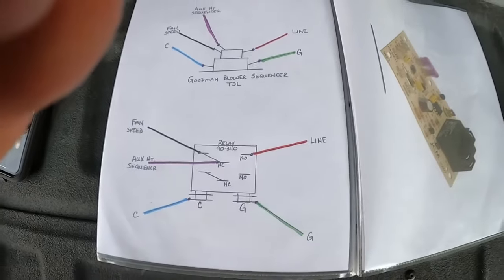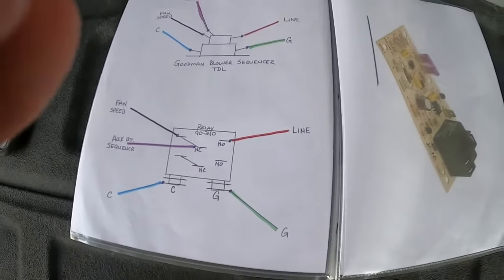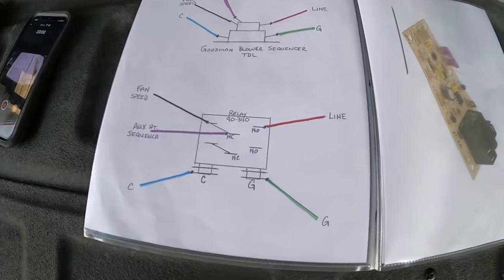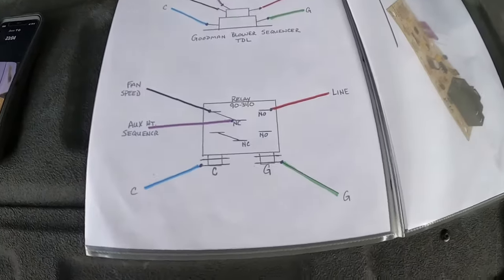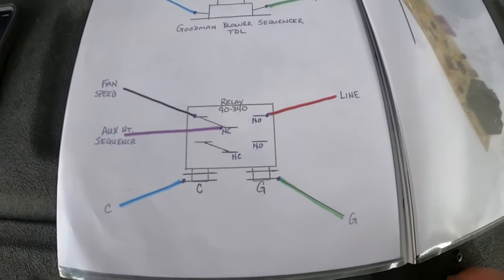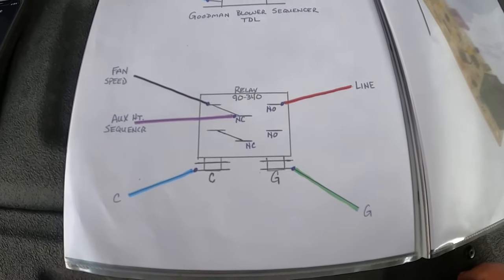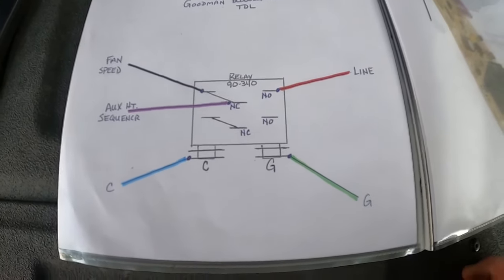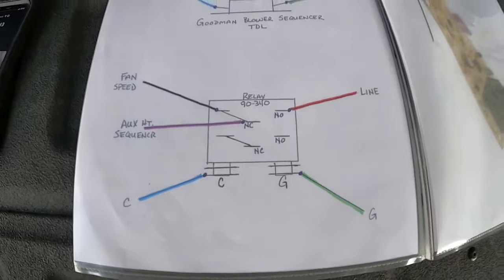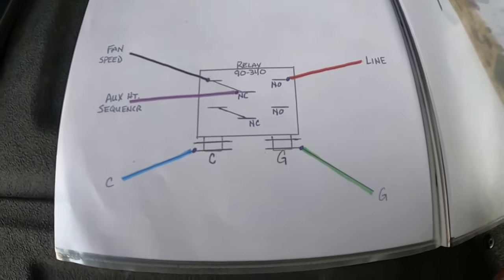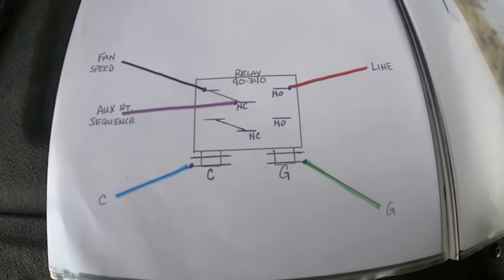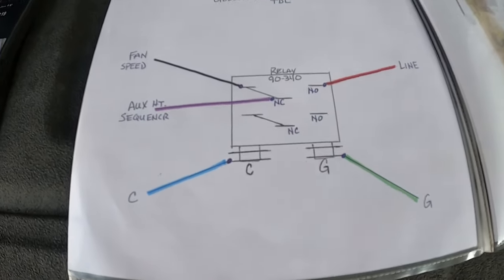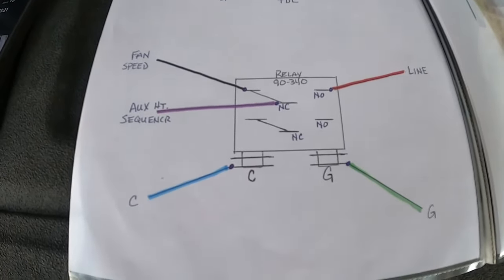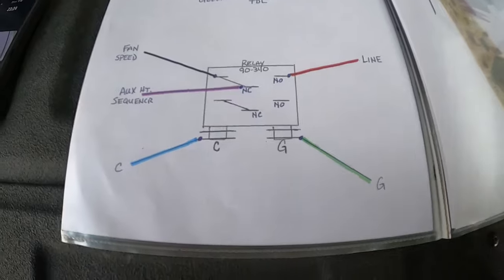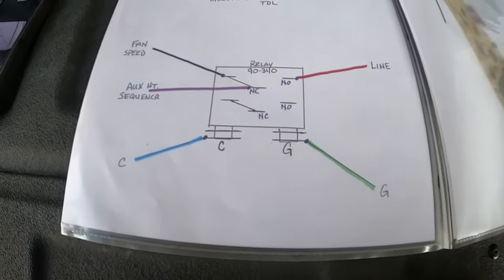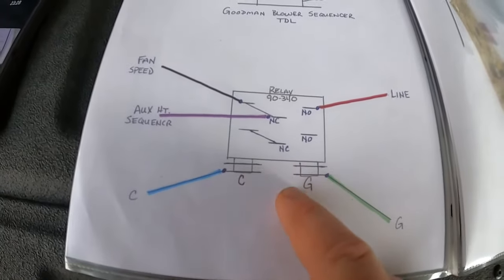But if you put your disconnect in, turn your breaker back on, the blower comes on immediately, and there's no call on G, then you wired something backwards. Start over. If you put your disconnect in and you've got 18, 19, 25, 30 amps, whatever you've got, and you're pulling amps and your blower's not running, you've got something wired wrong. If you put your disconnect in and nothing's running, and then you energize G and the heat strips come on, you don't have any airflow, something is wired wrong.